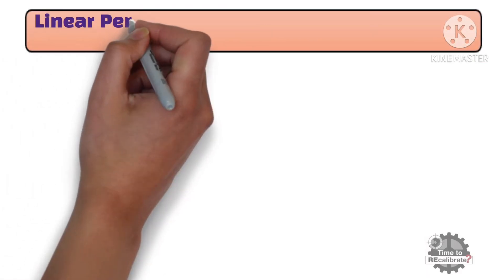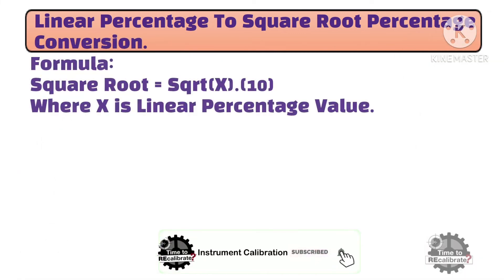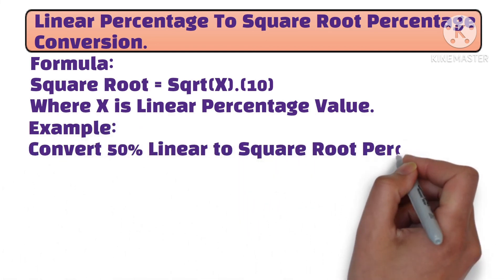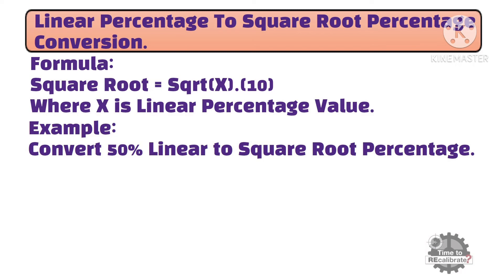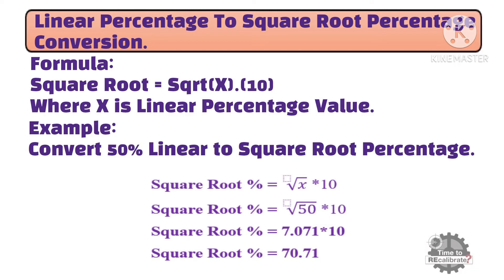Now, let's try to understand linear percentage to square root percentage conversion. This is a standard formula for linear percentage to square root percentage conversion, where x is the linear percentage value. For example, convert 50% linear to square root percentage. We put 50 into the formula: the square root of 50 is 7.071, which is multiplied by 10, giving 70.71.